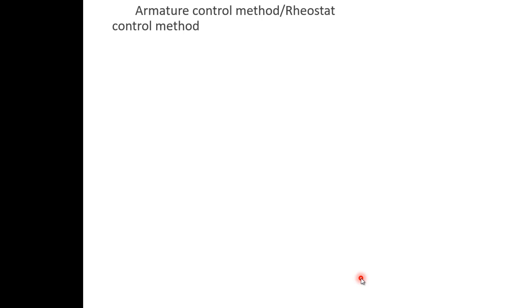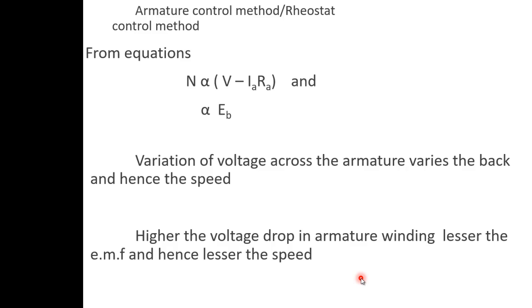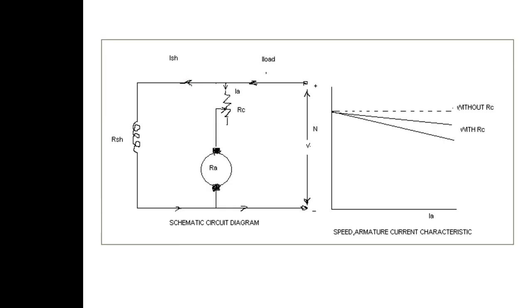Now we will see the armature control method, also called the armature rheostatic control or rheostat control method. From the equation, N is directly proportional to V − Ia×Ra, which equals Eb. So variation of voltage across the armature varies the back EMF and hence the speed. Higher the voltage drop in the armature winding, lesser the back EMF and hence lesser the speed.